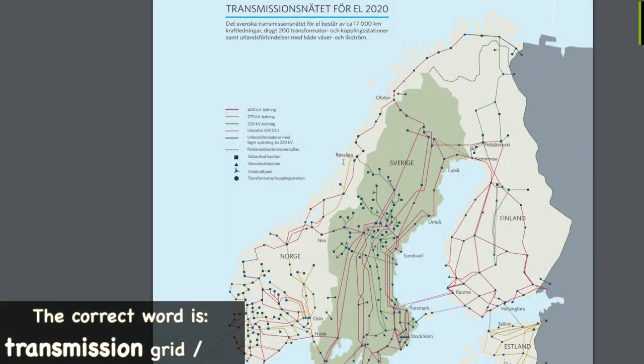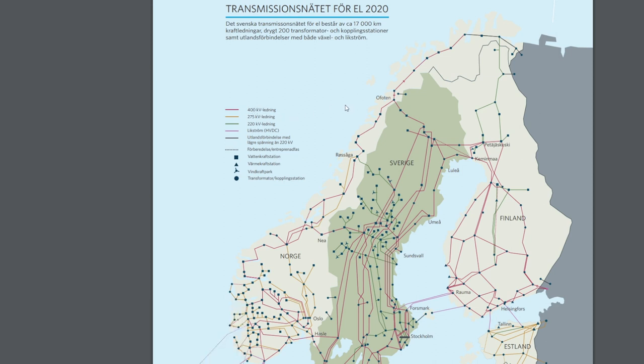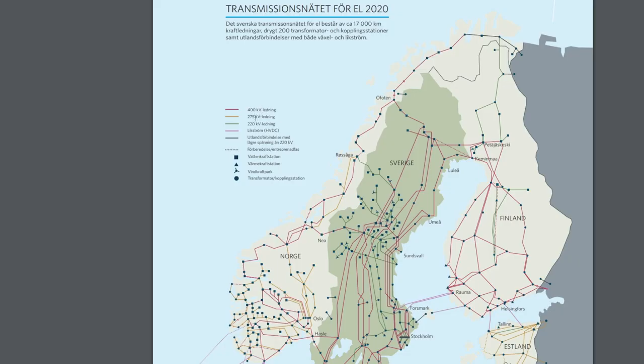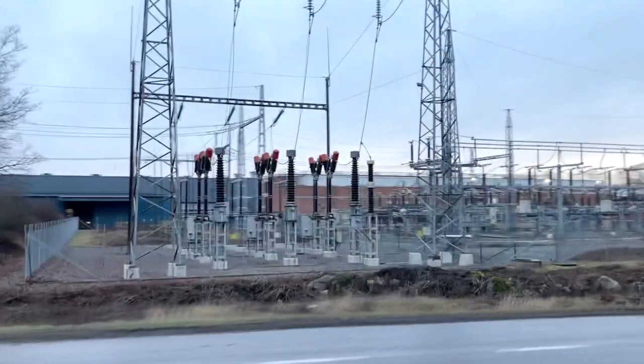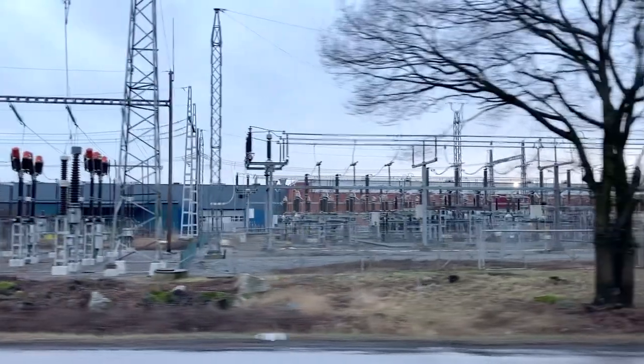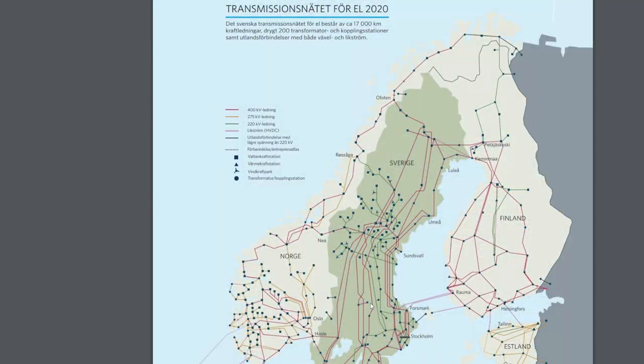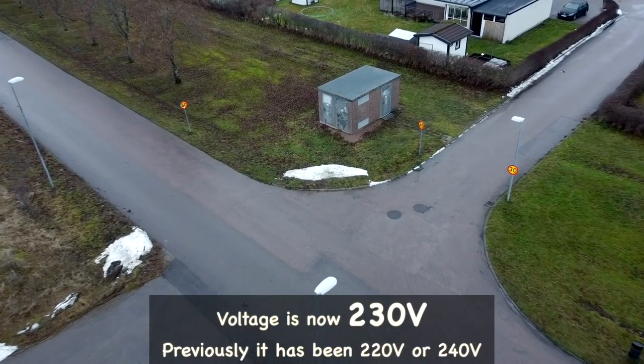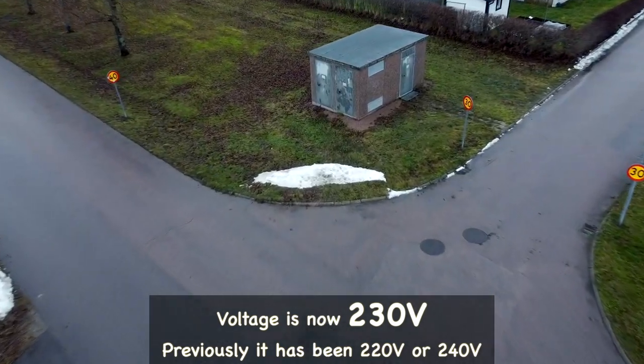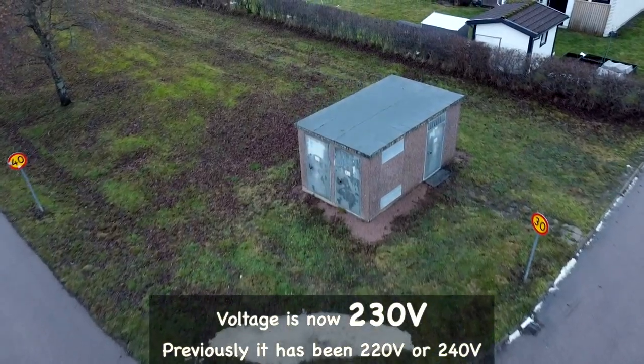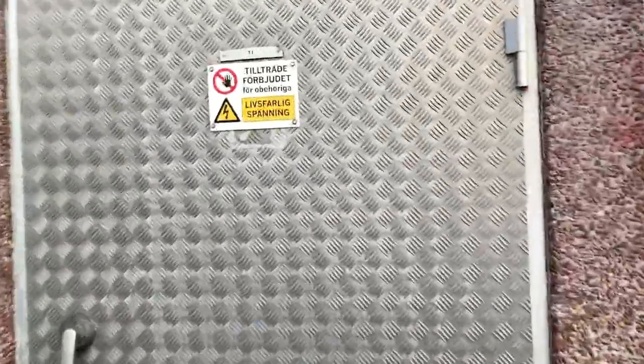In the transmission network, you have high voltage, like 400 kilovolts, because that gives lower losses. When closing in on the end consumers, like the wall outlet in your home, the power is transformed from 400 kilovolts down to lower voltages in what's called a transformer substation. In the local network, as close as possible to the home, there's a final transformation down to, in my case, 240 volts per phase. So the last transformation should be as close as possible to my wall outlet, because losses are high when the voltage is as low as 240 volts.